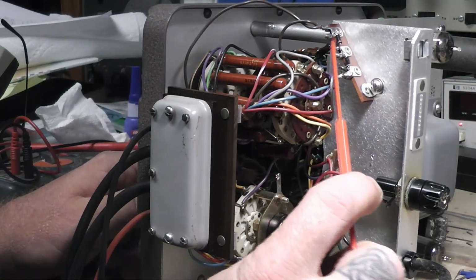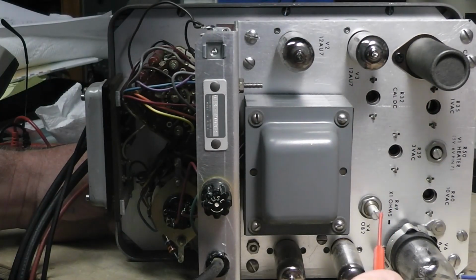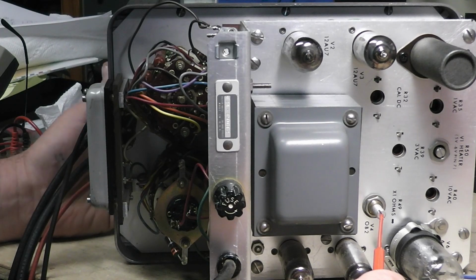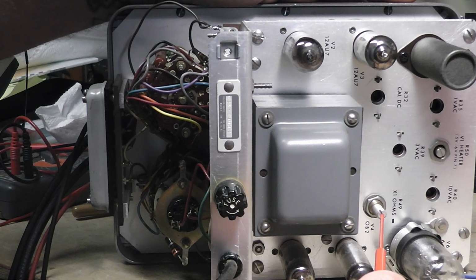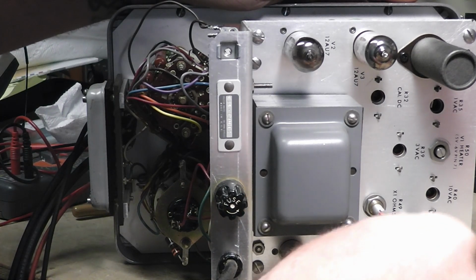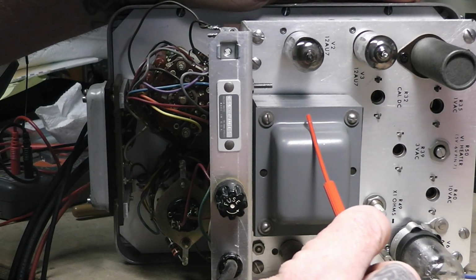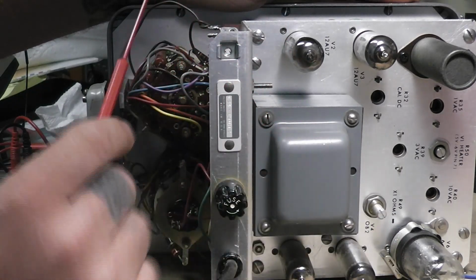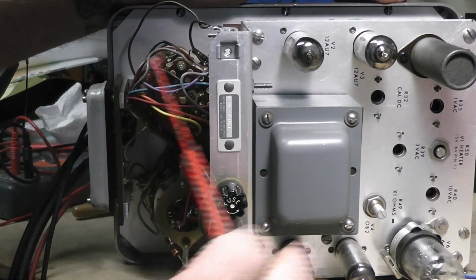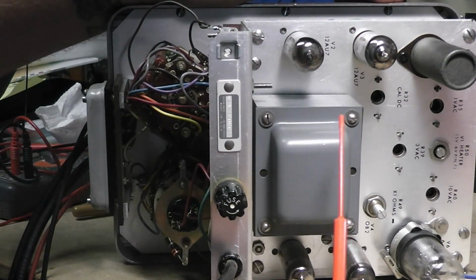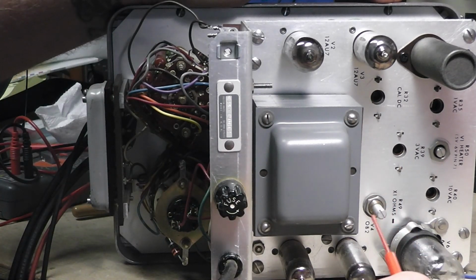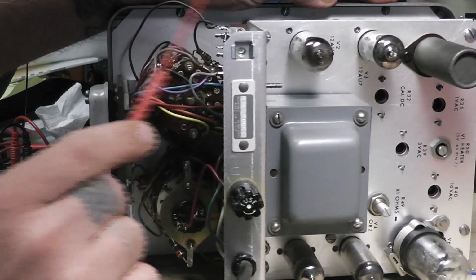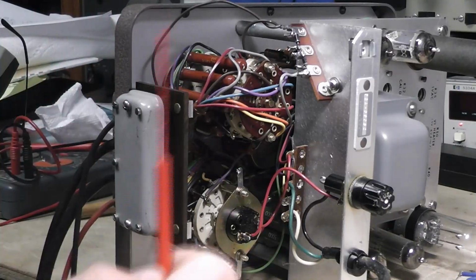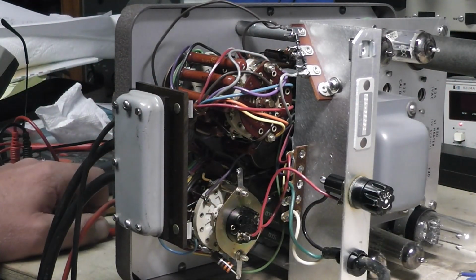So what I did find out was if I used one diode and adjusted this here to get it close to negative 1.2 volts, or close to where it reads on the face like it's supposed to, then I had to have this potentiometer all the way one way, almost to the stop. So you don't want to have something like that, as things change over time and age. These aren't so bad as selenium rectifiers, but other things in the circuit, resistors, get hot over time and kind of drift a little bit. If you have to come back and do just a quick realignment and not have to change any parts, you may find out where you have to, I ain't got no more to turn, it won't go no more. So by putting two diodes in, it brought it more so that the center is where it's at, so that's always a good thing.